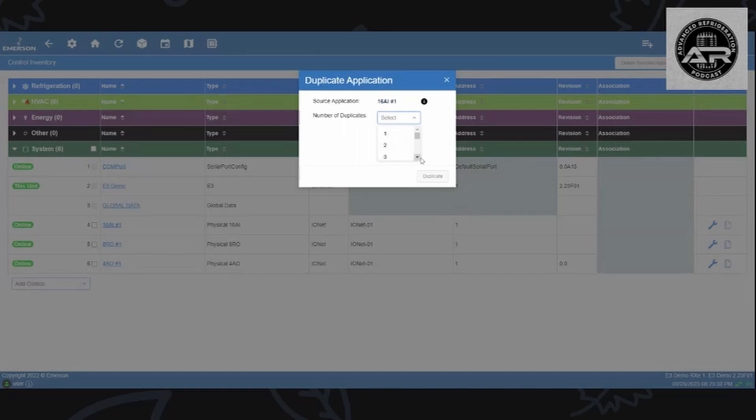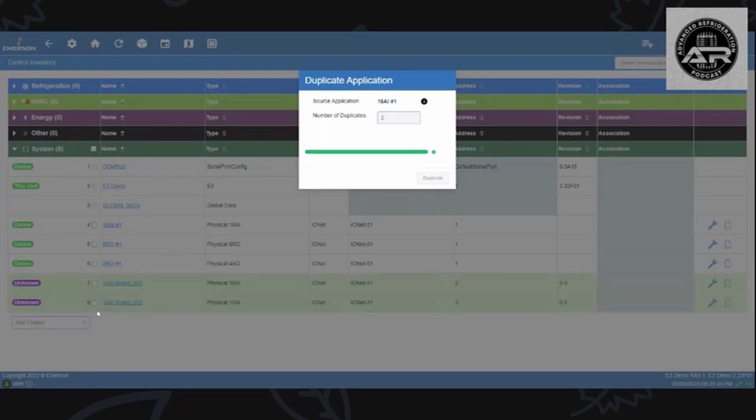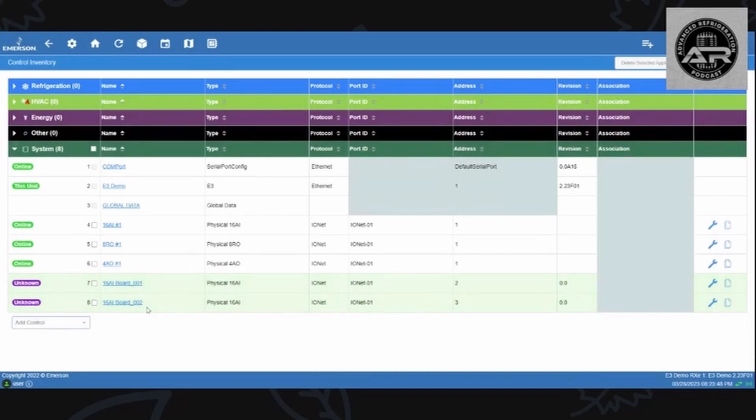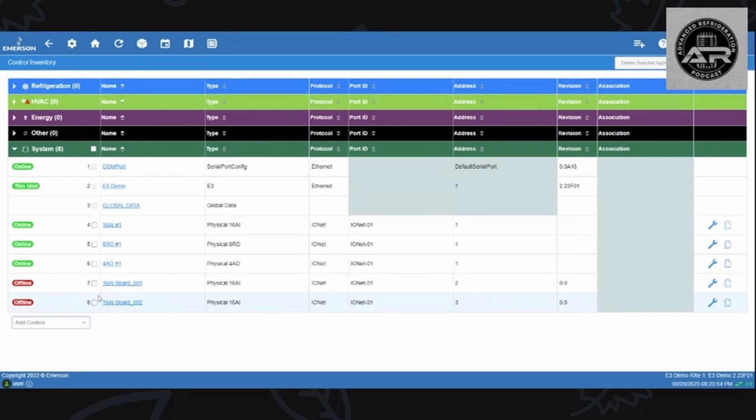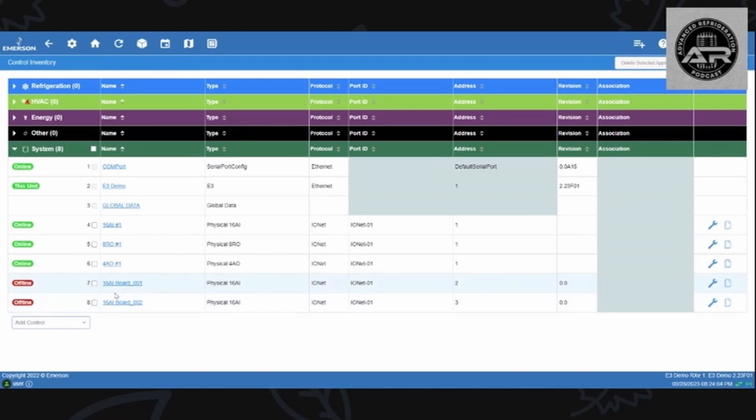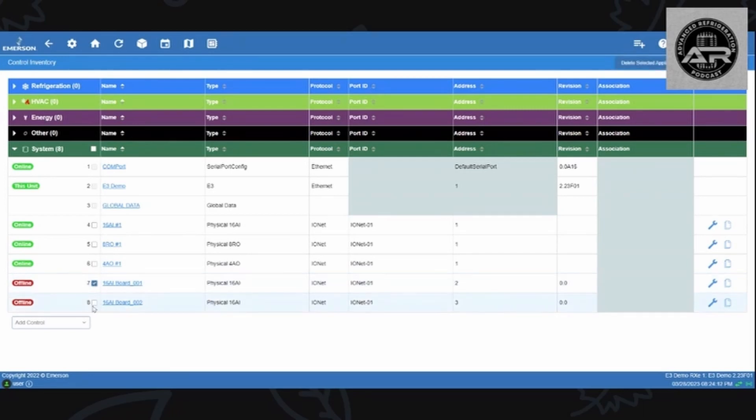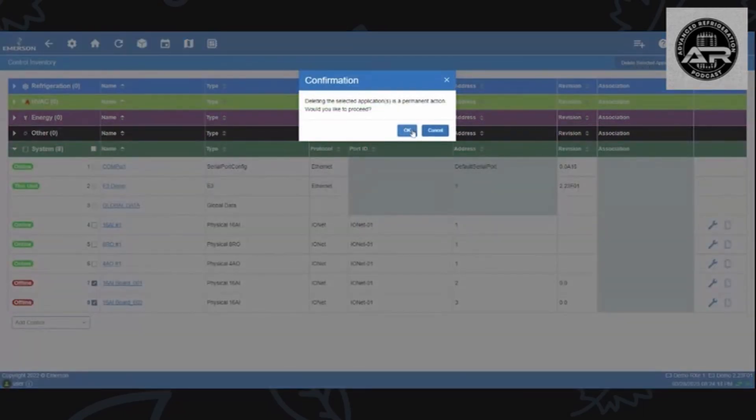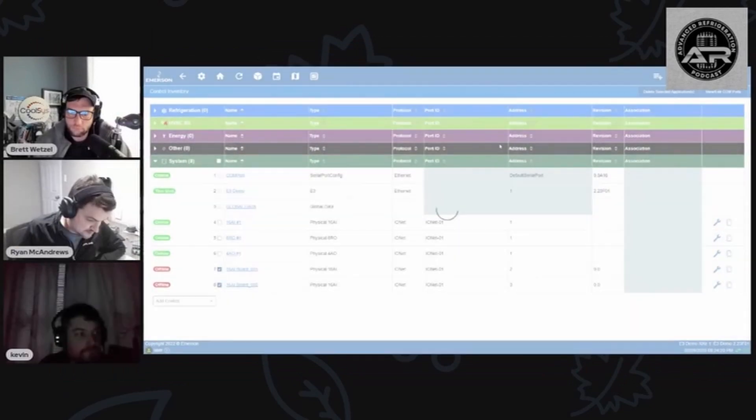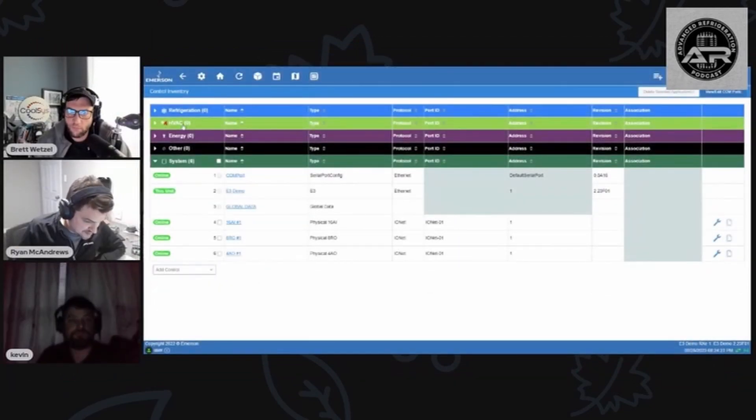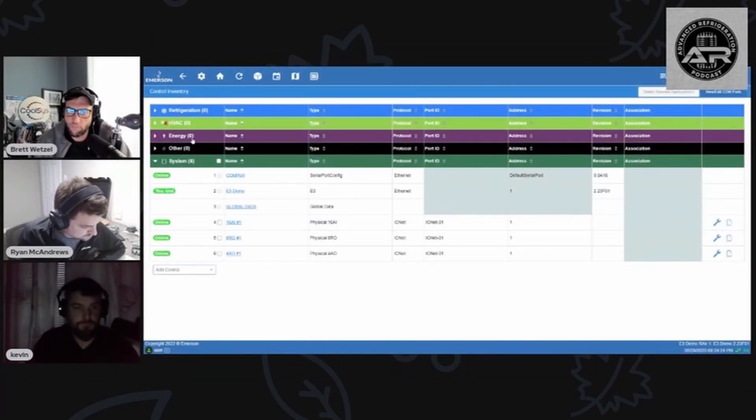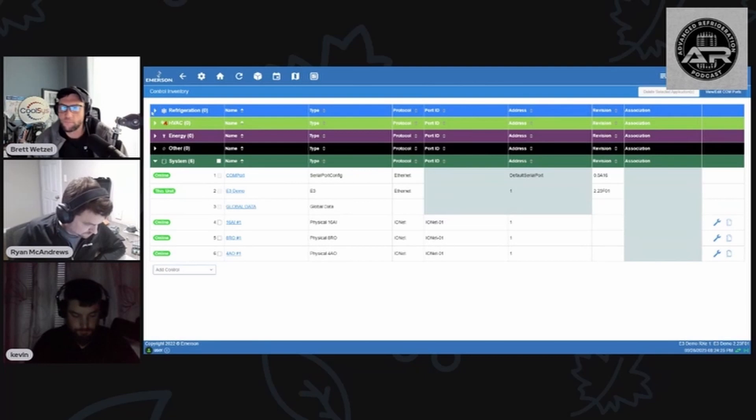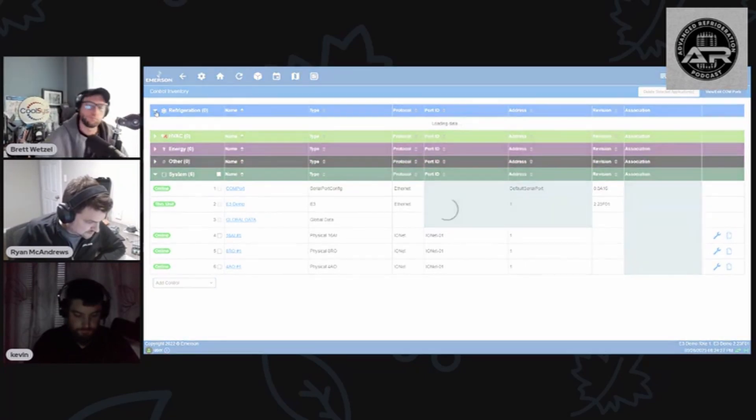If you want to add more boards that are going to follow a certain naming format, you can duplicate the boards. It's two little pages that are overlapping each other, click that and it's going to ask how many duplicates do you want. In this example I'll just choose two and duplicate it. I don't actually have these two boards connected to this E3 so it won't come up online but just to give you an idea on how to quickly duplicate it. That's the one you have behind you correct? Exactly, I have it in a little training case that I made up. If you made an error, right where it says online offline status there's a little check mark so you can tick it and move to the top right, you can delete the boards.